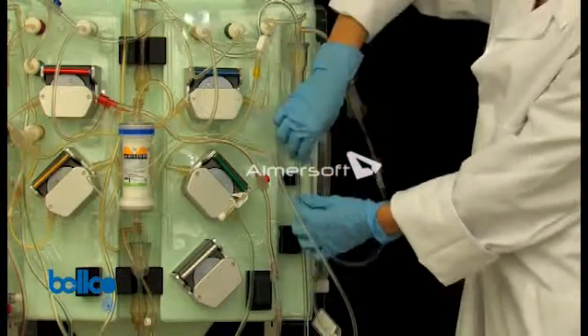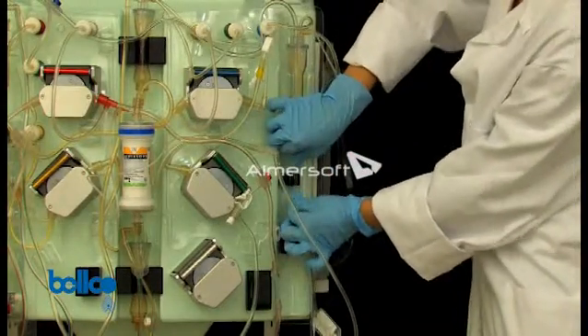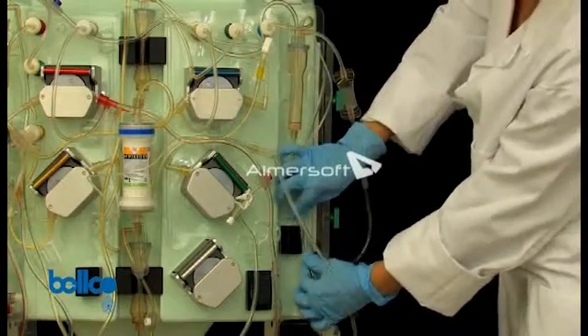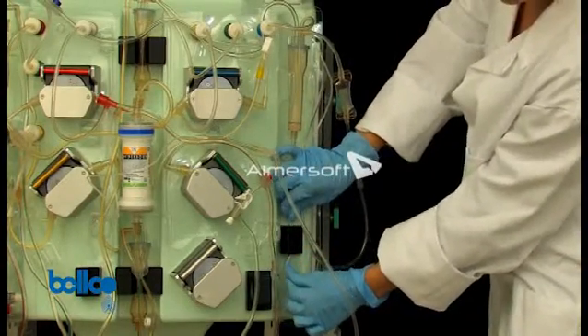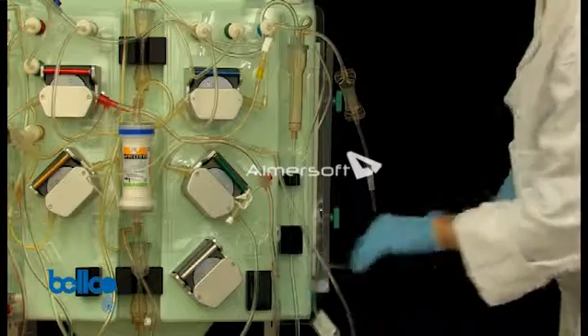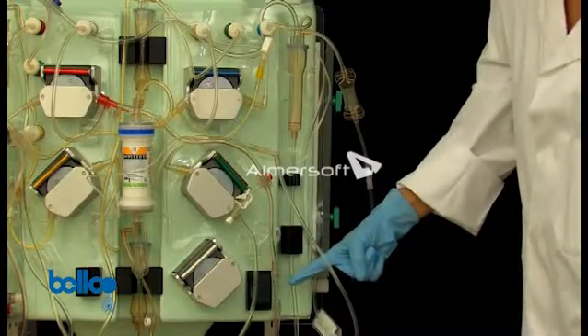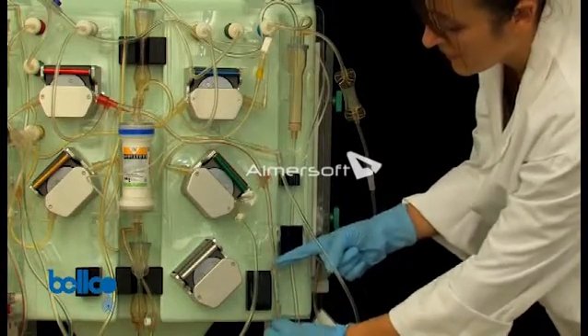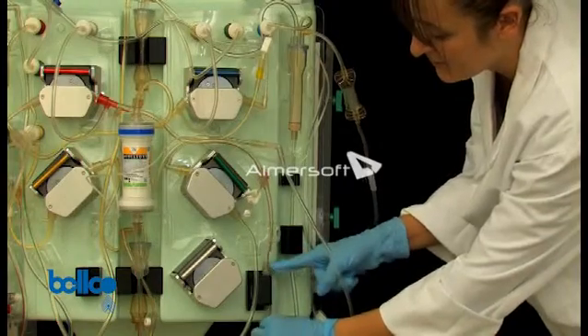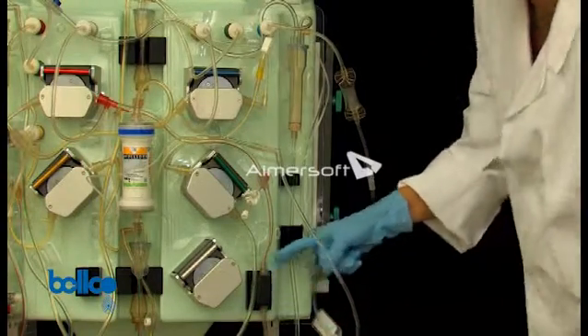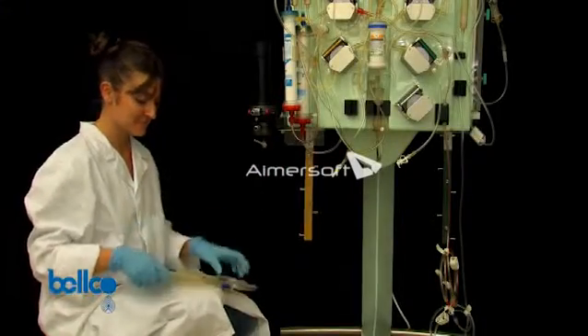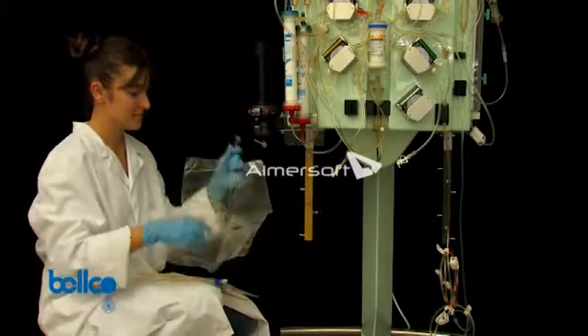Insert the venous line in the air detector and then in the venous clamp. There is a cuvette on the arterial line used to measure the hematocrit and oxygen saturation. Insert the cuvette in the dedicated holder. Now connect the waste bags.